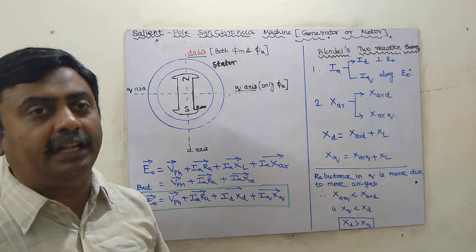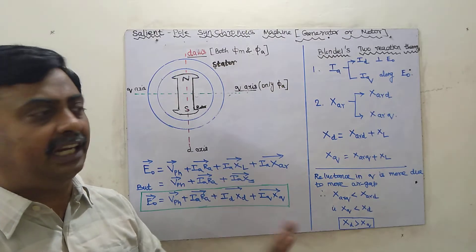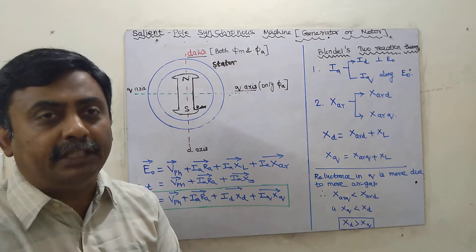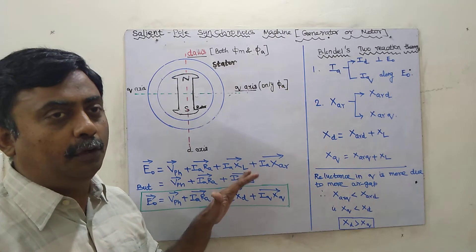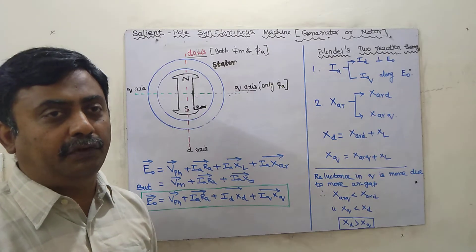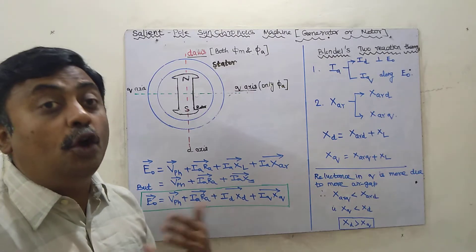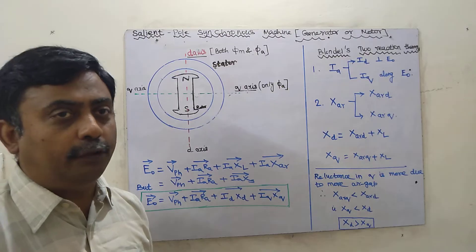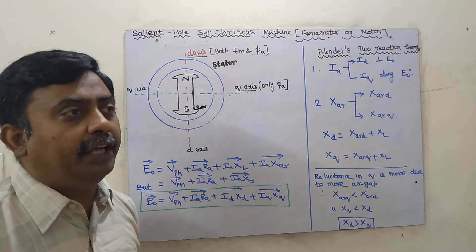Due to the non-uniform air gap, the reluctance in the field axis (D-axis) will be low, whereas along the quadrature axis the reluctance will be more. So the analysis we have already seen for non-salient pole alternators — using the EMF or MMF method — is not useful here. We have to go for a different method to find the voltage regulation.